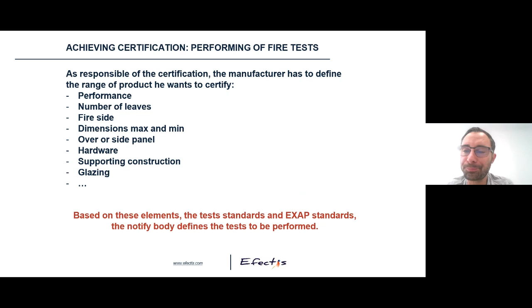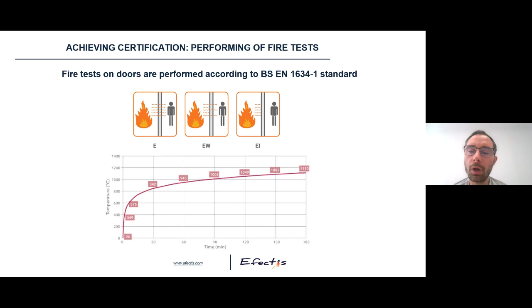So for people who are not familiar with fire testing, we will make some quick explanation of what fire testing is. So fire tests on doors are performed according to BS EN 1634 Part 1 standard, which defines the test to be performed. Regarding the performances of the fire doors that we can certify, we have the E doors, which are only fire integrity. We have EW, fire integrity plus radiation, and EI, which is integrity plus insulation. Tests are performed in furnaces under what we call the ISO 834 curve, which is a cellulosic fire curve, which has been used in many countries for many years.